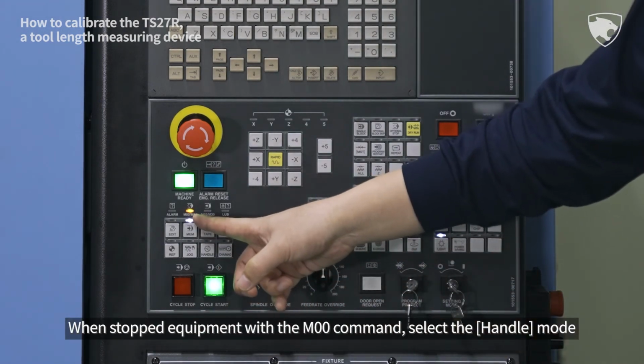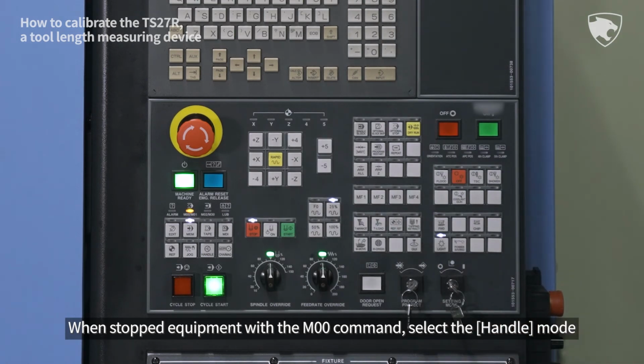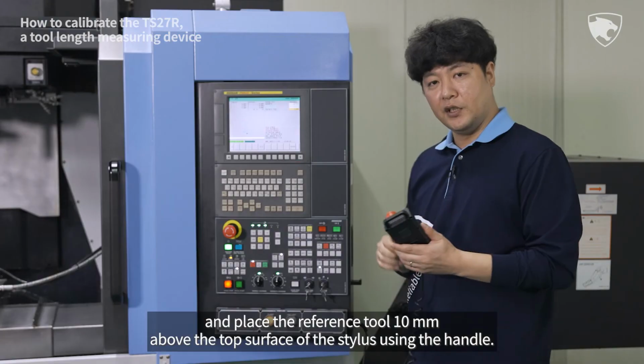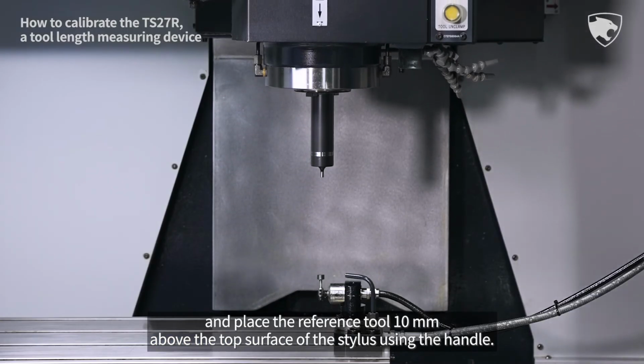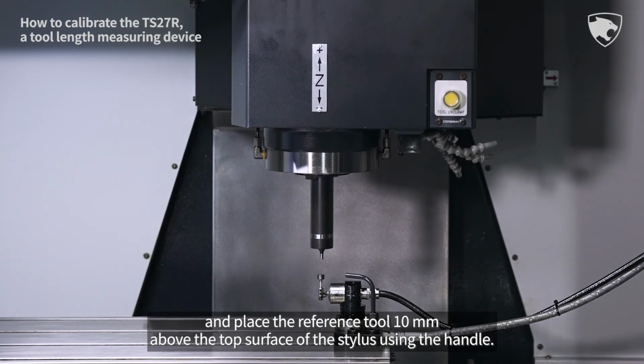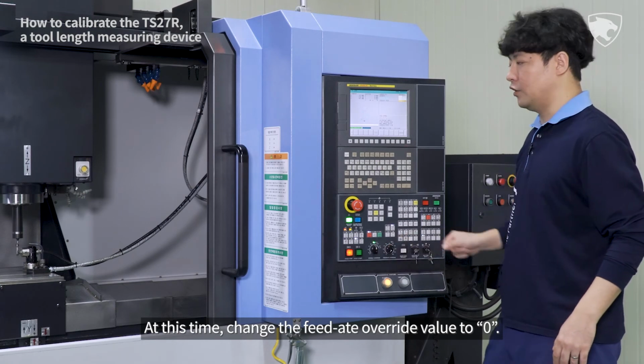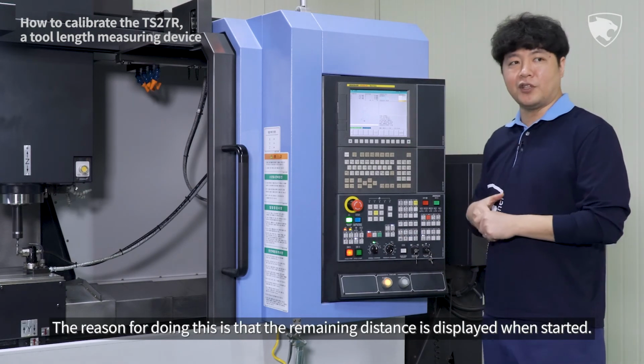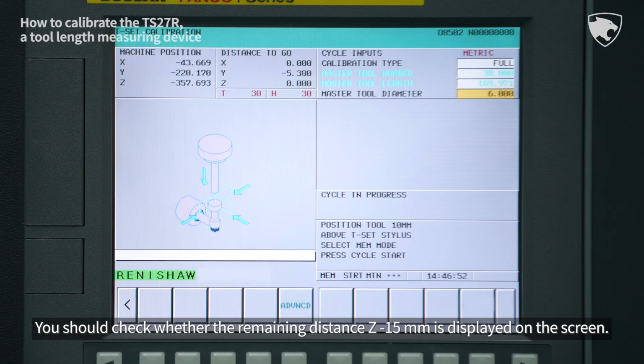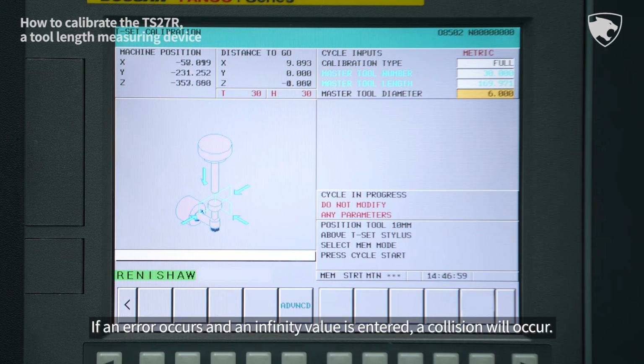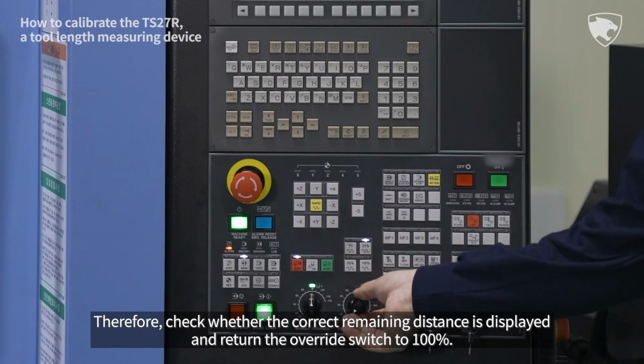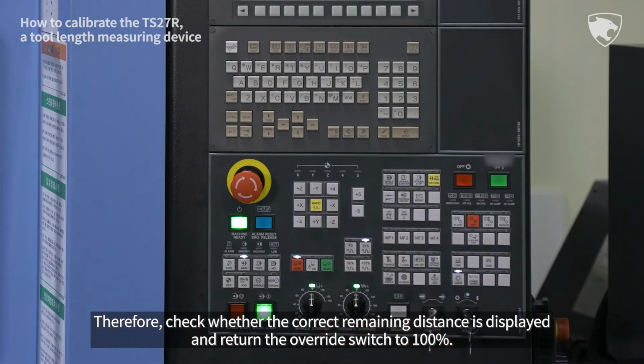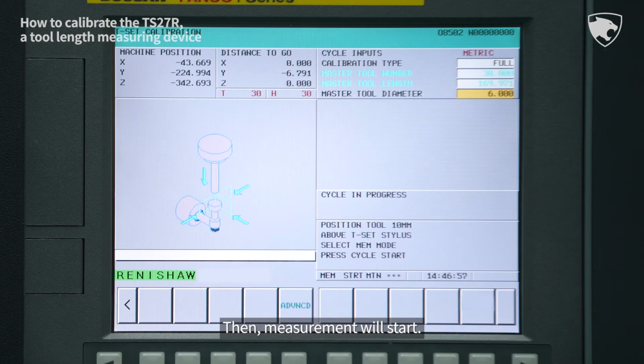When the equipment stops with the M00 command, select the Handle mode and place the reference tool 10 mm above the top surface of the stylus using the handle. At this time, change the Feed override value to 0. The reason for doing this is that the remaining distance is displayed when started. You should check whether the remaining distance Z minus 15 mm is displayed on the screen. If an error occurs and an infinity value is entered, a collision will occur. Therefore, check whether the correct remaining distance is displayed and return the override switch to 100%. Then, measurement will start.